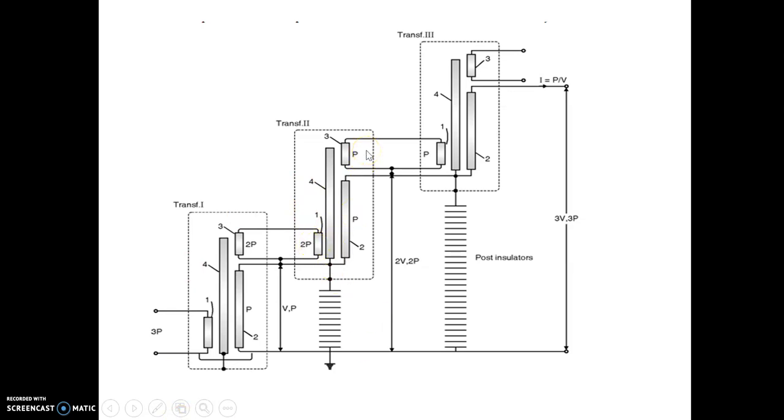Again this should be 100 volt. We see tertiary winding 100, and this may not be there because you are not using another stage here. So this 100 and this 100, and this will be 100 kilovolt. So what will be the loading? You may see the same voltage, 100 volt, 100 volt, 100, but the loadings will be different. Now see, from here you will understand there should not be any load on this because you are not giving supply to this. What will be the load on this?